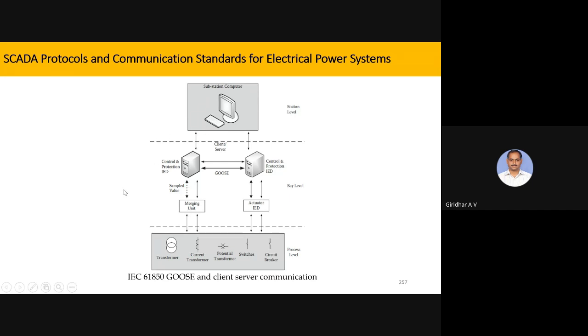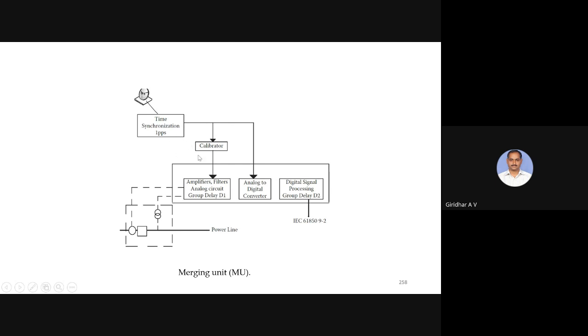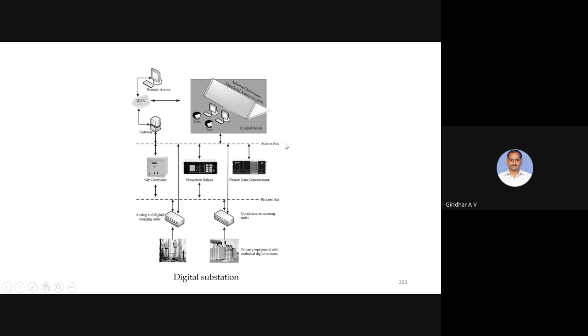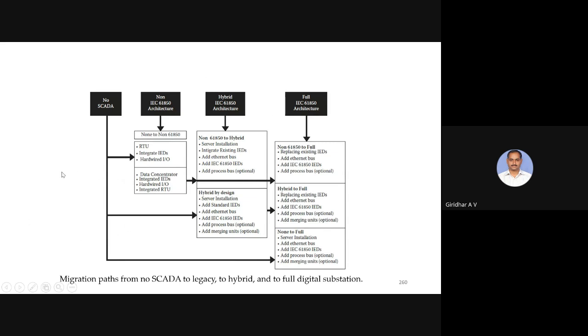Very fast, critical functions can all be done using this process bus through the IEC standard 61850. Even time synchronization can be done, as per these protocol standards. You can see all digital substations using the process bus, breaker control, protection relays, appropriate protections. Even phasor data they will handle, and use it for appropriate actions through the phasor measurement units. Typically you can see the advancements, without SCADA, just within that RTU.